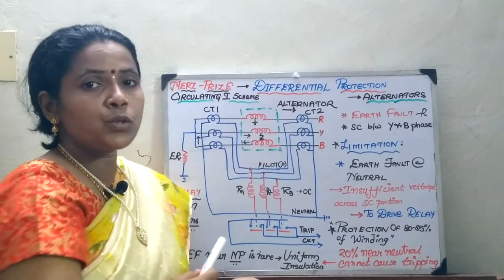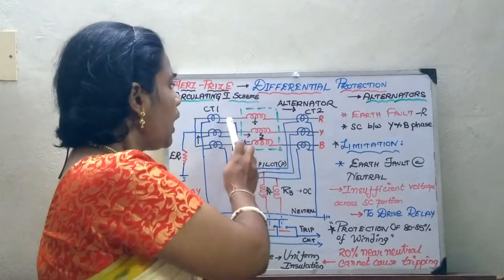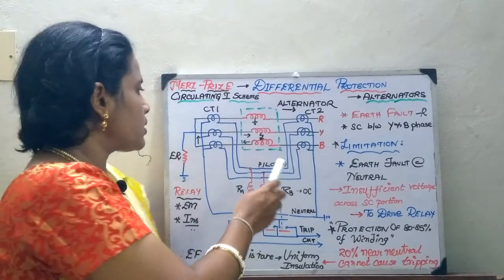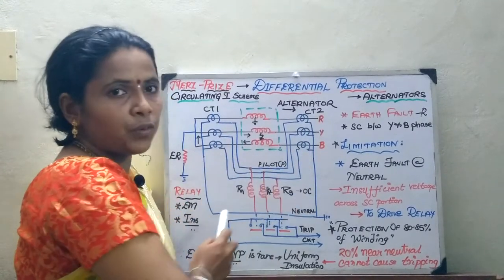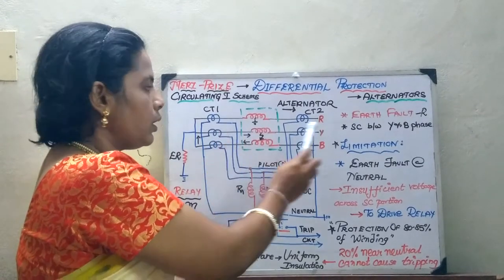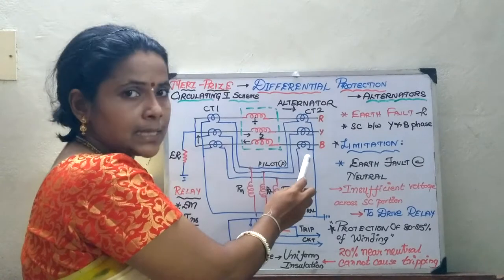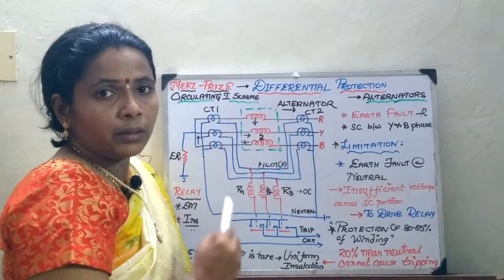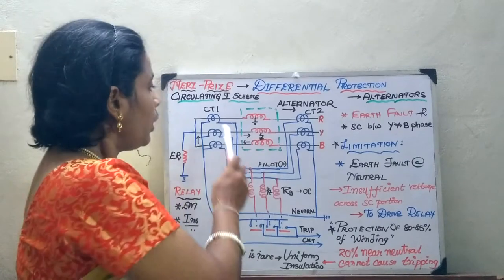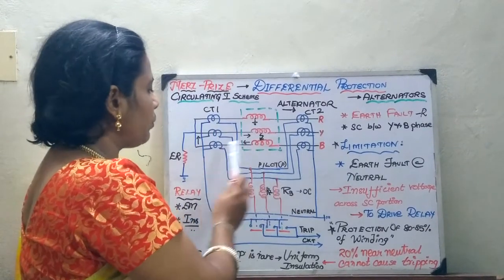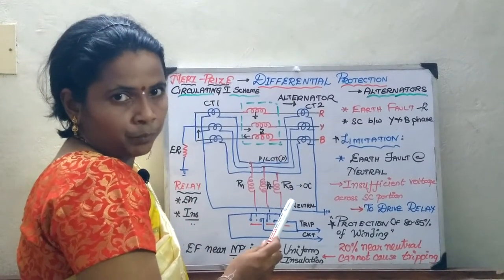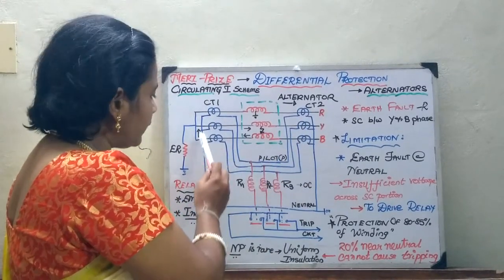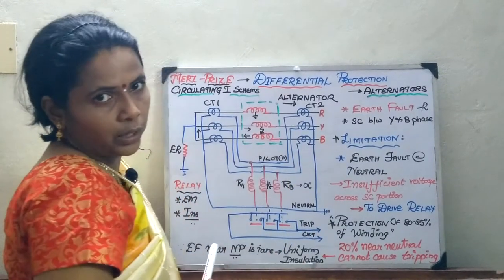Now we will see how to draw the circuitry. First, draw the three-phase winding — R, Y, and B phase. Then connect the CTs from both ends; in each phase R, Y, B, CTs are connected so that current can be taken from their secondaries and connected to the relay coil. In this case, star-connected CTs are used on both sides, and both star ends are grounded.